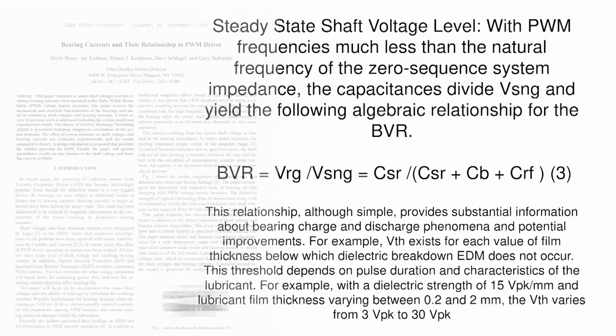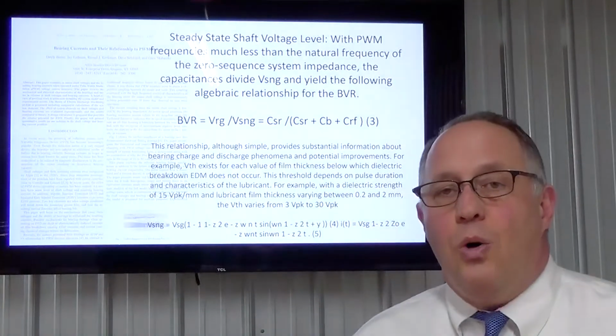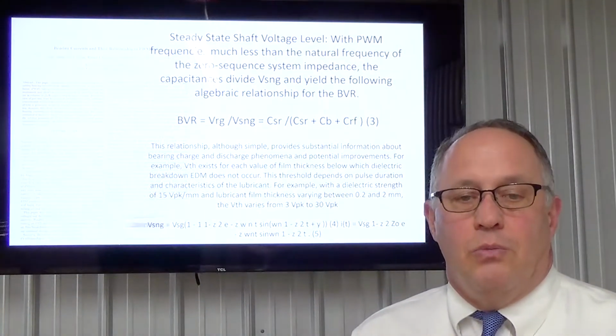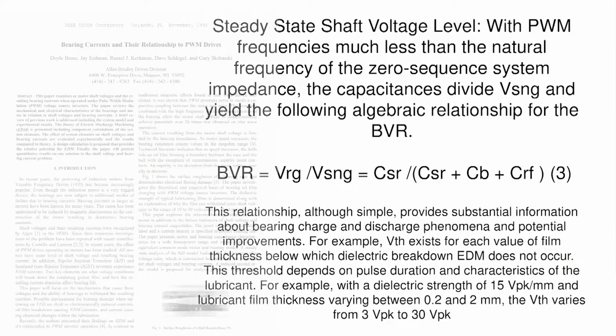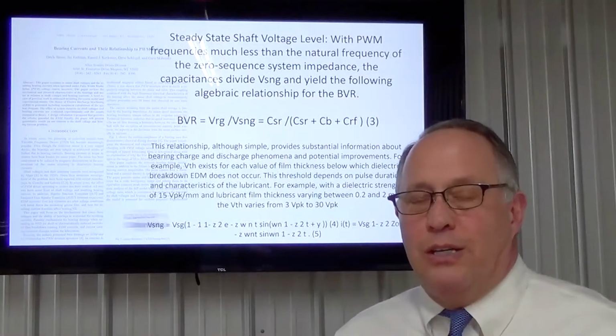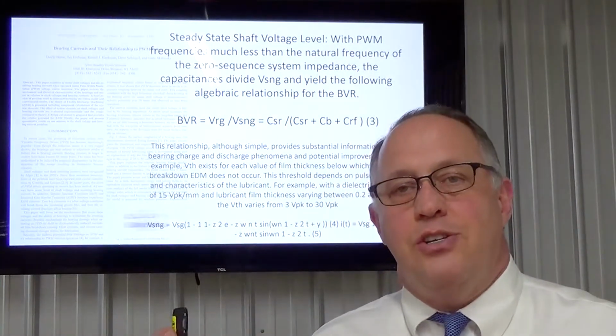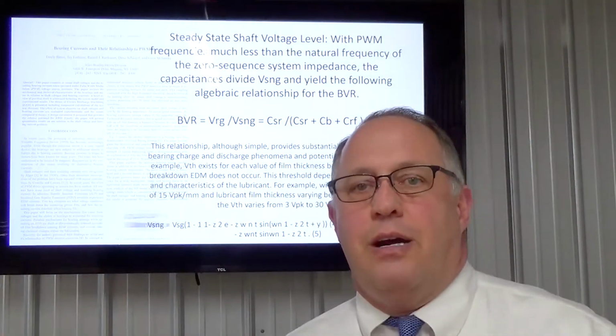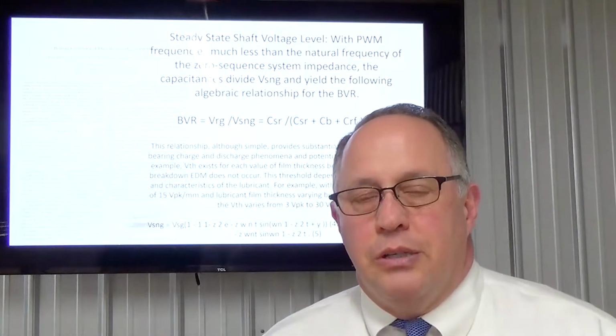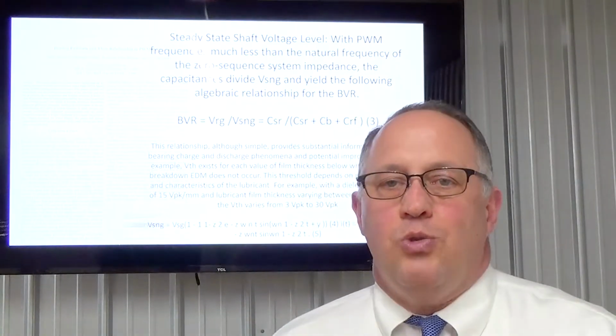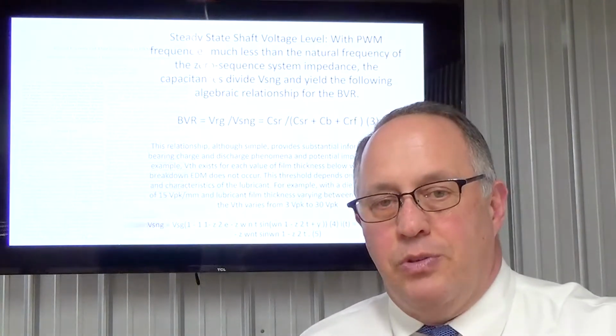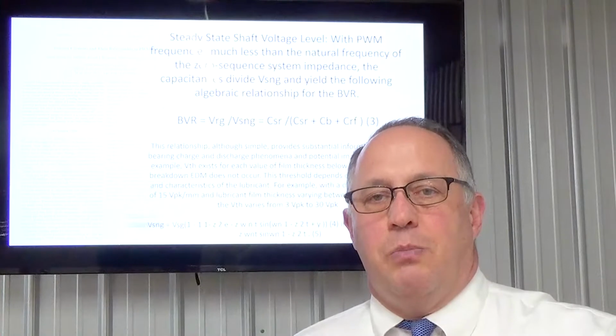These studies and white papers will come away with all types of reasons for the failure, what we're talking about. They have concluded this one, bearing currents in their relationship to PWM drives show that there are frequencies less than the natural frequency of zero sequence system impedance. The capacitance divided the voltage and yield the following algebraic equation. If you were to take a look at the equations in this, they're about 12 variables long. Now, those variables will tell us the individual components that make up this type of induced shaft voltage. But let's just break it down.